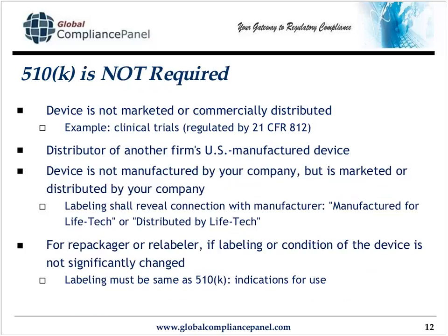There are situations in which a 510K is not required. A device isn't marketed or commercially distributed. Perhaps you're doing clinical trials. The devices are never leaving your control, or a CRO, clinical research organization, that's operating as your firm, so to speak. If you distribute another firm's U.S. manufactured device, you're just a distributor. You're not the manufacturer.